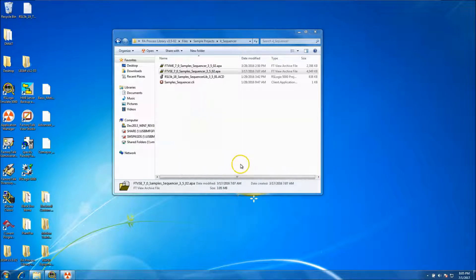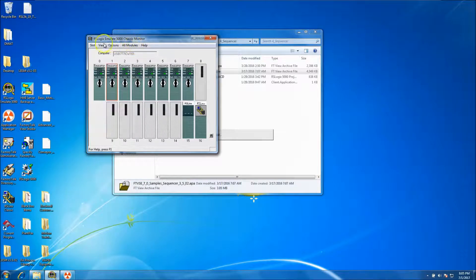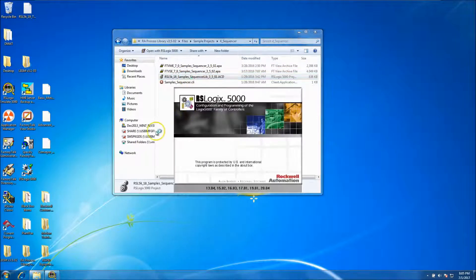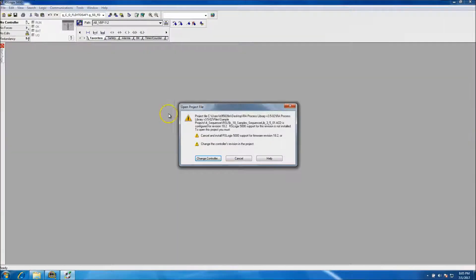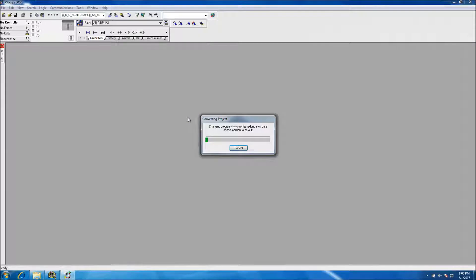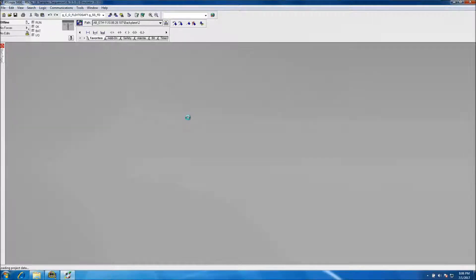This will be done off our RS Logix Emulate 5000 chassis, so we're going to go ahead and open our program. This is created on version 18. I don't have version 18, but I have versions under and above that, so it's going to prompt me to change the controller. I'm going to change it to an emulator, change it to version 20, and let it make the program — it converts everything over.